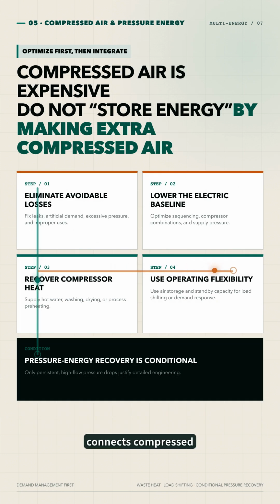The fifth type connects compressed air and pressure energy with other systems. Most of the electricity entering an air compressor ultimately becomes heat. A stable compressor station can recover that heat for hot water, cleaning, drying, or process preheating. Air receivers, network pressure, and standby compressors also provide a degree of load flexibility. Compressors can avoid high price periods or participate in demand response. Where a large and continuous pressure drop exists, pressure energy recovery may also be assessed. But compressed air is an expensive secondary energy carrier. Never manufacture extra compressed air simply to claim storage value. Leakage, artificial demand, and excessive pressure must be corrected first.